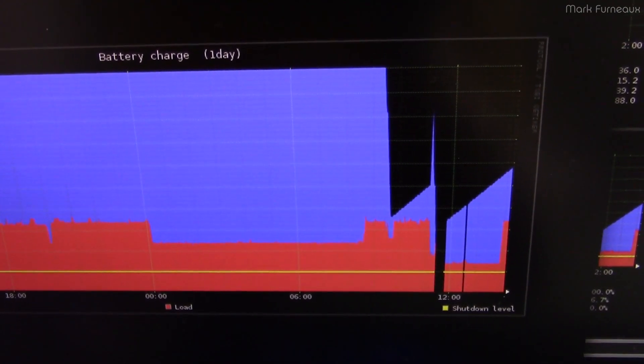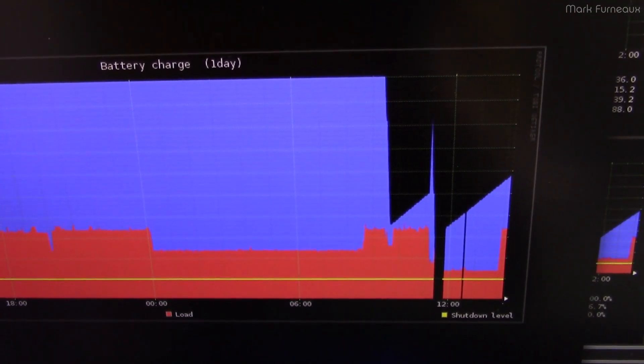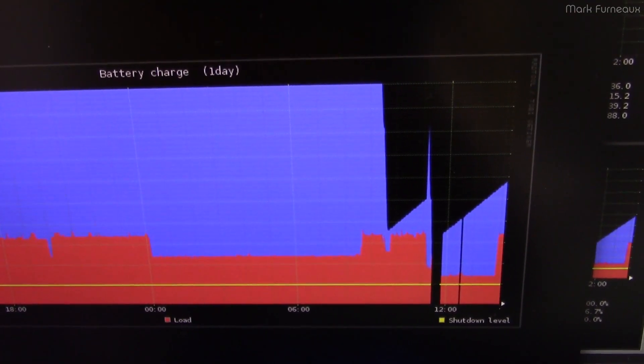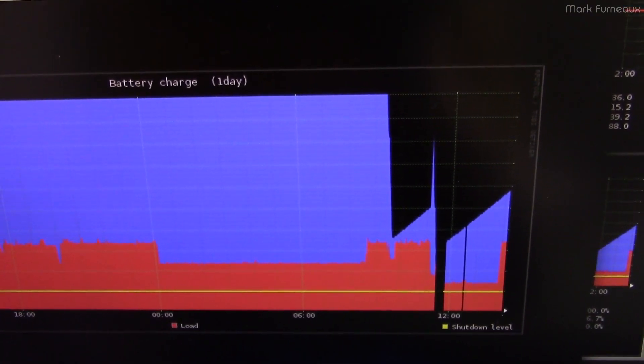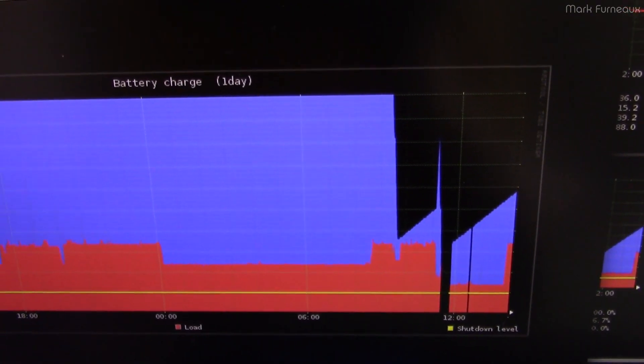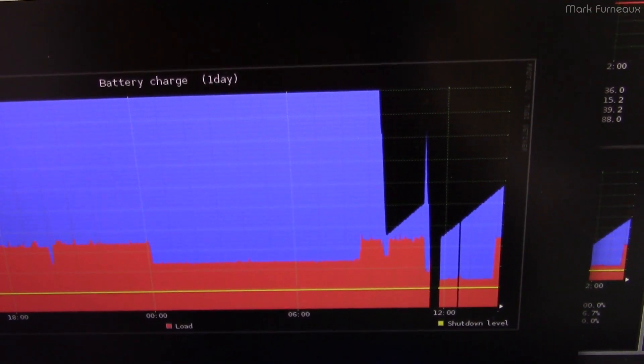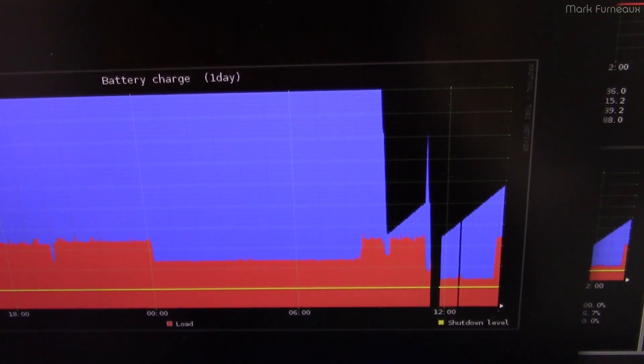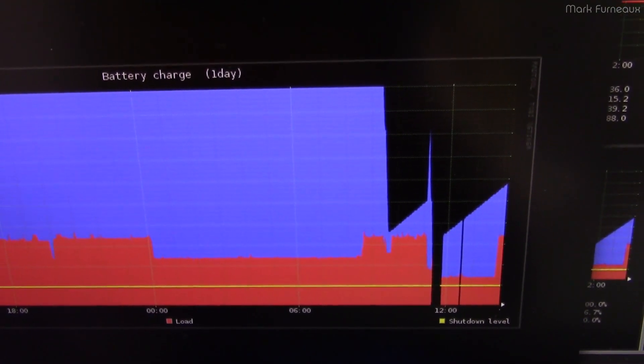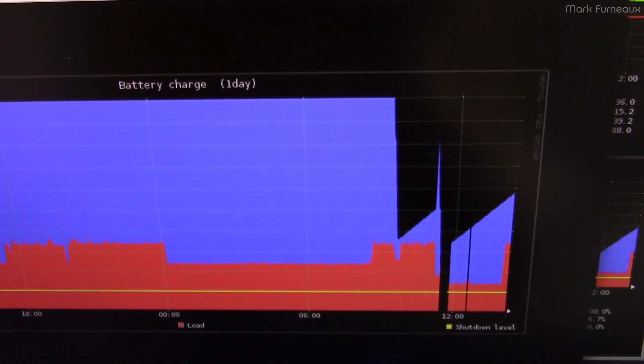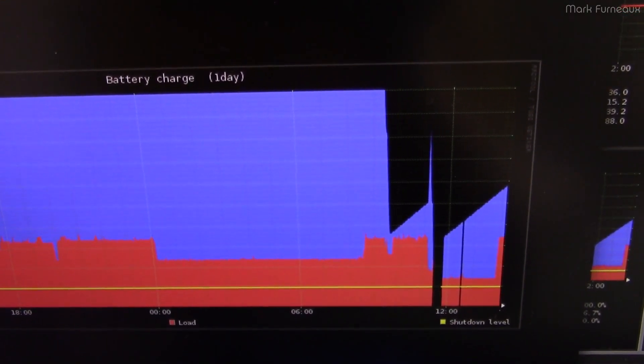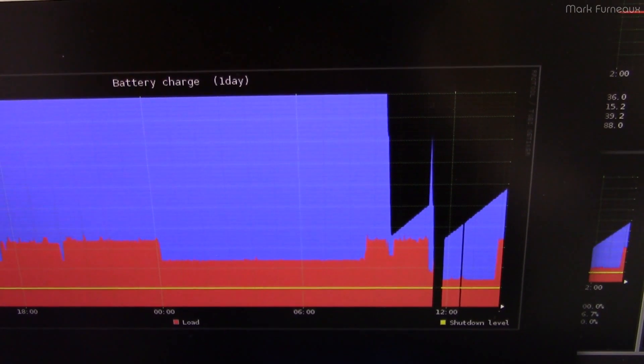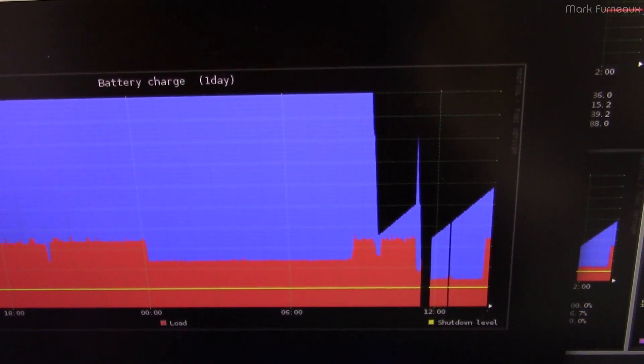Maybe somebody knows. But yeah, it's just kind of funny. And if you've got a UPS and when you're charging it, don't go by the percentage. So if you're going to do some sort of test on your UPSs, or you're going to do some planned power maintenance or whatever, make sure you charge the batteries for a long time before you do your discharge. Because going by the percentage, at least on this UPS, it doesn't mean anything.